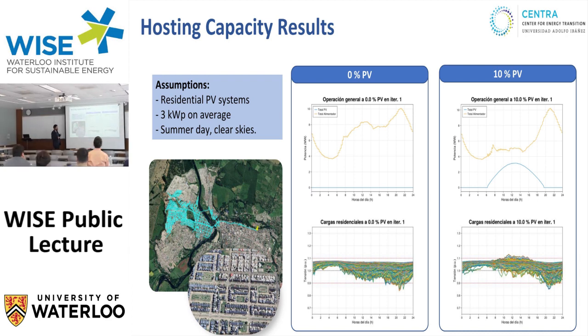Then we started integrating distributed generation and observing what happened. For example, these are the results for voltage: if you start integrating more and more photovoltaic, you'll see high voltage during the day, peaking when PV generation is highest and load is low, resulting in high voltage at the end of the feeder. That's the technical limit violation that will limit the hosting capacity.